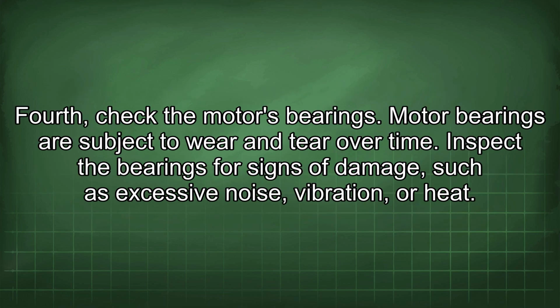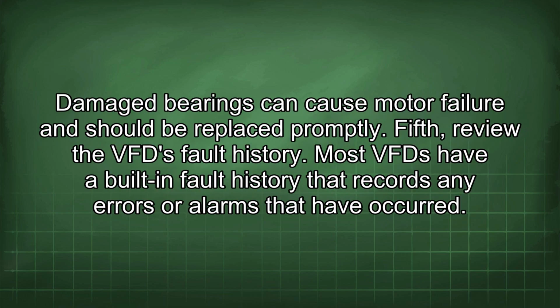Fourth, check the motor's bearings. Motor bearings are subject to wear and tear over time. Inspect the bearings for signs of damage, such as excessive noise, vibration, or heat. Damaged bearings can cause motor failure and should be replaced promptly.